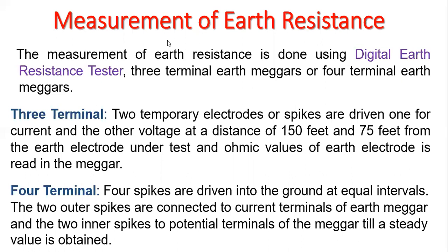First of all, the measurement of earth resistance. There are different equipments by which we can measure the earth resistance. The measurement of earth resistance is done by using a digital earth resistance tester, a three terminal earth resistance measure, or a 4-terminal earth resistance measure. So let us see one by one.